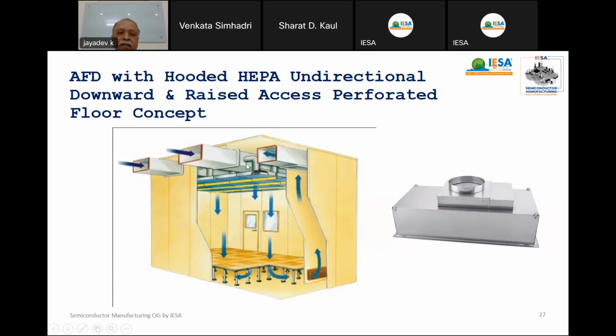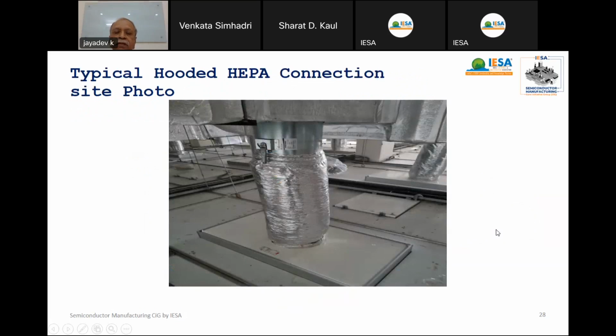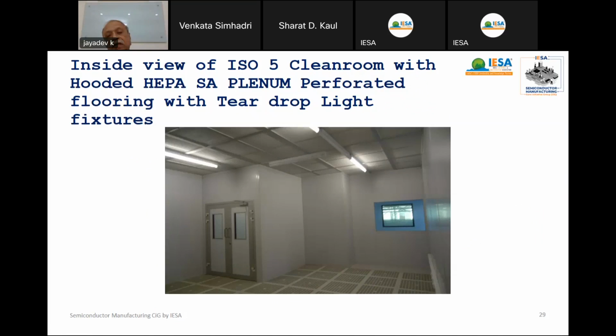So you can see the supply duct and return duct coming from that. Here what we are fixing is this hooded HEPA. This is about 300 mm depth, same size, and there is a round collar for the flexible duct and a filter fixed inside. This is another method of achieving it, using hooded HEPA filters. How we connect from the supply duct through a flexible duct to the hooded HEPA looks like this in the clean room. And the result is a class 100 clean room with perforated flooring and all. Particularly in this case, we have to use this for class 100.